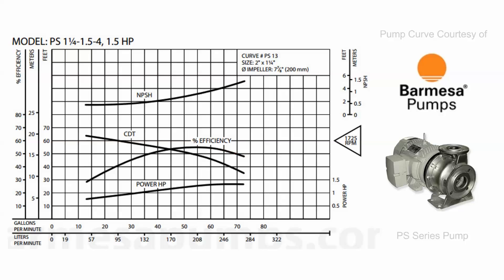This curve also shows the horsepower requirement to achieve the designated flow and head rating. They show the horsepower rating on the right-hand side — half horsepower, one horsepower, and one and a half horsepower. You can see that there's really no reason you would want a half horsepower, because at no point does half horsepower achieve the workload of the pump's capability. Once we get into one horsepower, that motor can handle from one part of the curve to another without overloading.